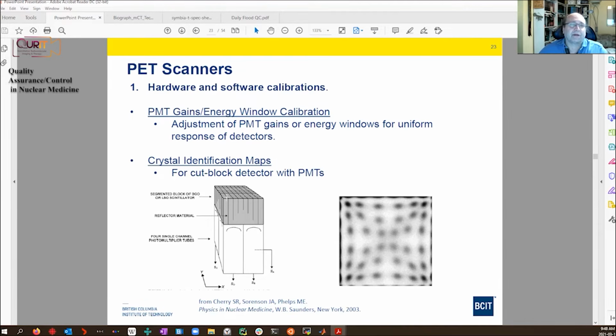Again, the idea is each of these acts like its own independent detector, and the resolution in PET depends on how small you can make the detector. And so when a gamma ray hits one of these crystals, there's cuts such that the pattern of light going to the 4 PMTs will vary in such a way that you should be able to identify which of these 64 crystals the gamma ray hit. So here's an example of what we call a crystal identification map. So if you flood the detector and you ask which crystal was hit, you see that they're not evenly spaced.